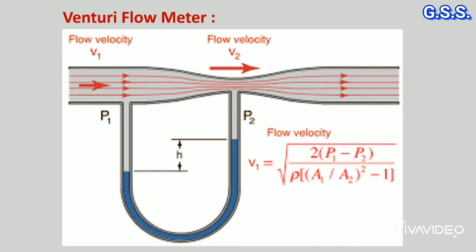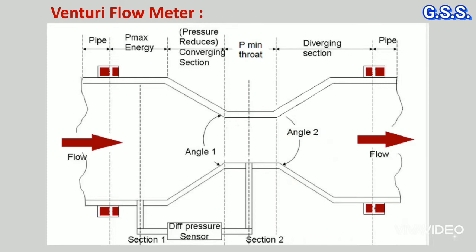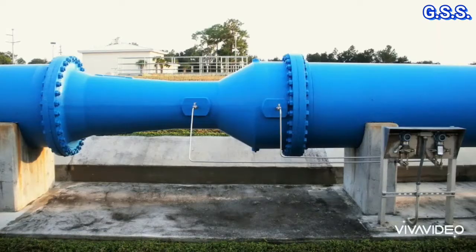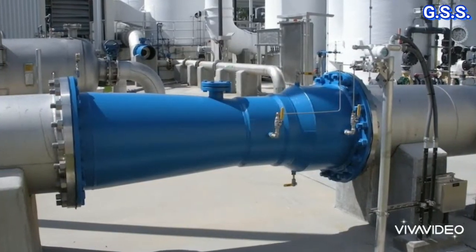The advantage of venturi flow meter is about 90% of pressure drop is recovered in the diverging section, which is not possible in orifice flow meter. This is an installation of venturi flow meter.